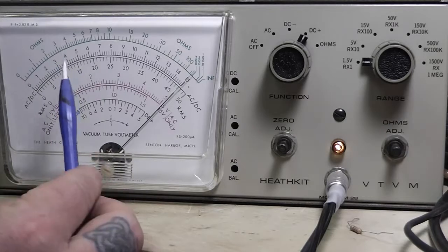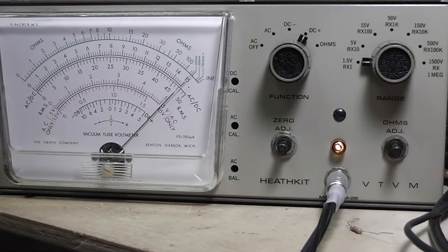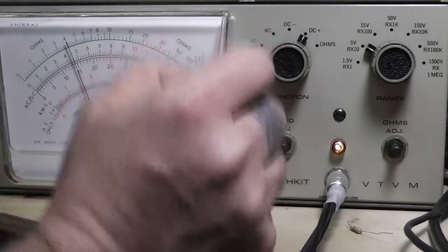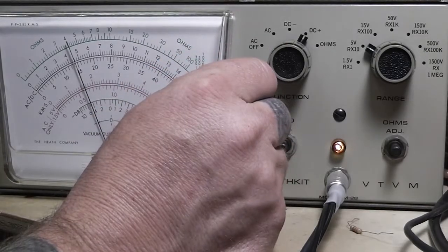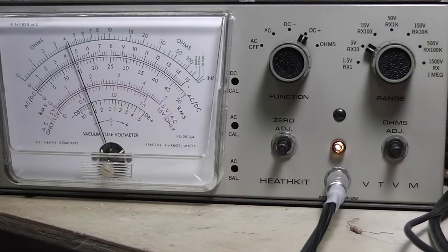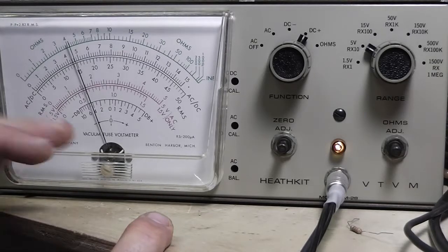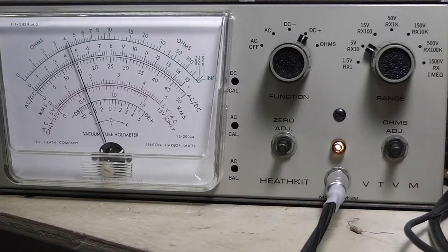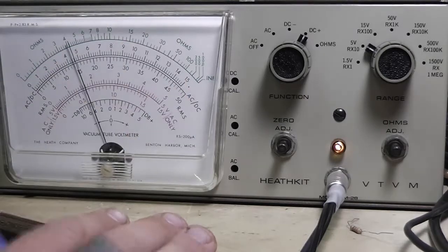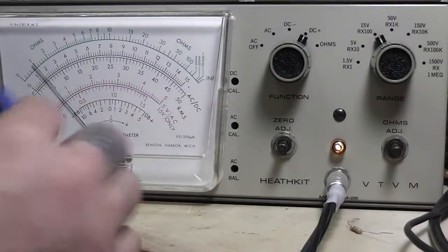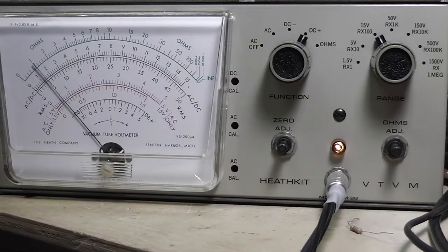And when I move this switch up into 5 volts, 1.5 volts should read right here at 15. Now it may be off just a little bit. It's not going to be perfect with these meters, and it's a hair off. What you can do too is calibrate these things to use a different voltage, 5 volts or whatever. If you're going to be using the 5 volt scale a whole lot with whatever testing you're doing, calibrate on the 5 volt scale. If you're going to be doing a lot of testing with, say, 12 volts or 13.8 volts and things like that with ham radio or whatever, go up here to the 15 volt scale and calibrate on the 15 volt scale. So that's reading, yeah, that's right at 1.5 volts right there.